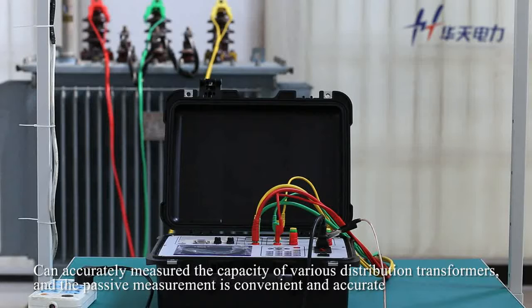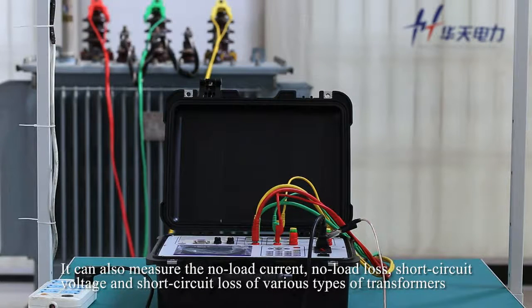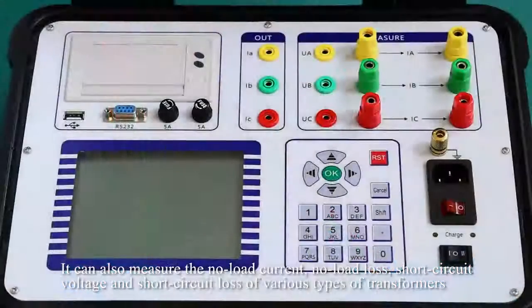It can accurately measure the capacity of various distribution transformers, and the passive measurement is convenient and accurate. It can also measure the no-load current, no-load loss, short circuit voltage, and short circuit loss of various types of transformers.